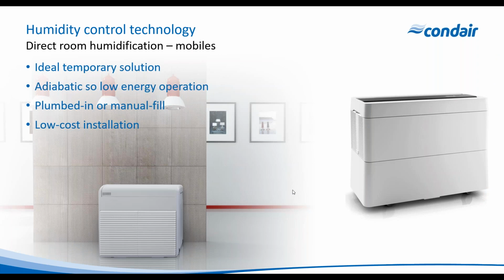And very common is mobile units. So here, when we've got no air delivery method and we're in a public area, a mobile unit is an ideal situation, although we do have to get over the aesthetics. It's very difficult to hide these units, so they are something that is going to be in a public area and in public view. But they're ideal for a temporary solution, and they're adiabatic, so low energy operation. Again, we're using the heat energy in the air to offset the adiabatic cooling, so they're nice and cheap to run, and it's a low cost installation. And you can have them plumbed in, or you can have them where they're just refilled manually. So a really good solution, especially if you want to move them, so that they are mobile.